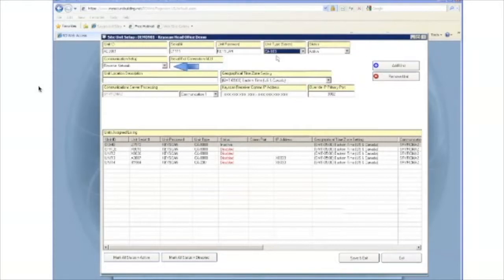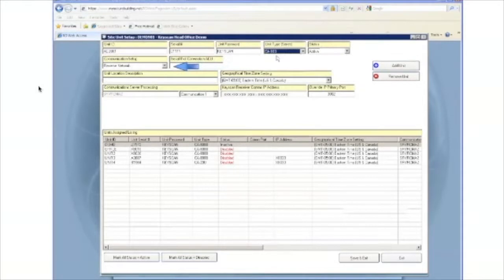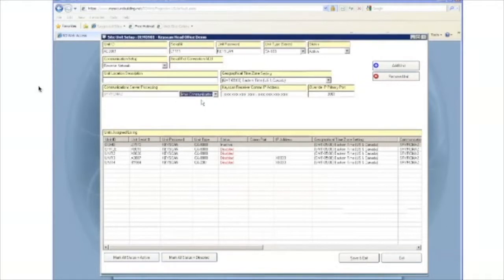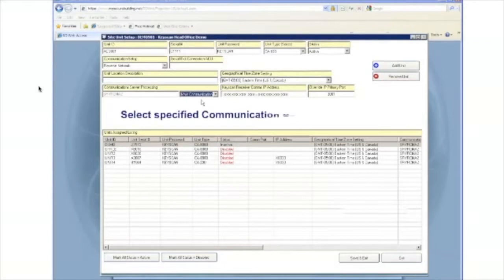Under communication setup, reverse network should already be selected. The following fields of information that we're going to enter should be provided to you by Keyscan. You may need to select the communication server processing, which is the communications manager that the panel will be connecting to. You have an option of main, communications 1, 2, 3, or 4. Once again, choose that which was provided to you.